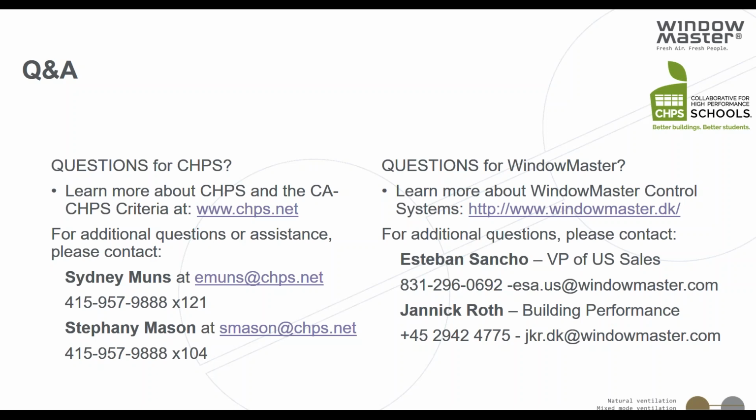There's a question, and it looks like this is for you, Jannick. Are the window controls easily integrated with a BMS on a BACnet communication protocol? Yeah, so actually we have multiple things we can do. We can either do it with the BACnet control system. We can also do it with some other protocols called KNX or LON, or Modbus. So actually, there are different protocols that can be used. From our perspective, we do either the BACnet or we can also do the KNX, LON or Modbus solution.